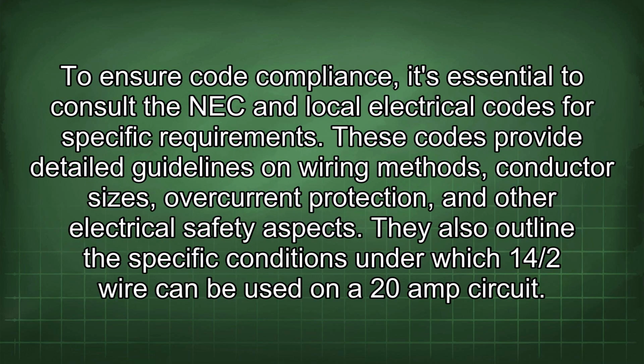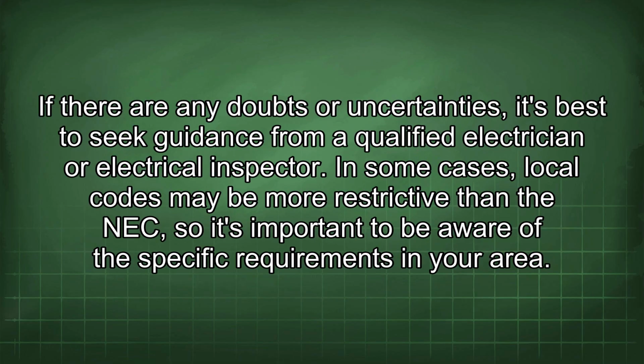To ensure code compliance, it's essential to consult the NEC and local electrical codes for specific requirements. These codes provide detailed guidelines on wiring methods, conductor sizes, overcurrent protection, and other electrical safety aspects. They also outline the specific conditions under which 14/2 wire can be used on a 20-amp circuit. If there are any doubts or uncertainties, it's best to seek guidance from a qualified electrician or electrical inspector. In some cases, local codes may be more restrictive than the NEC, so it's important to be aware of the specific requirements in your area.